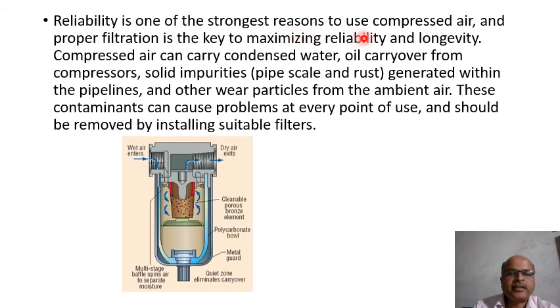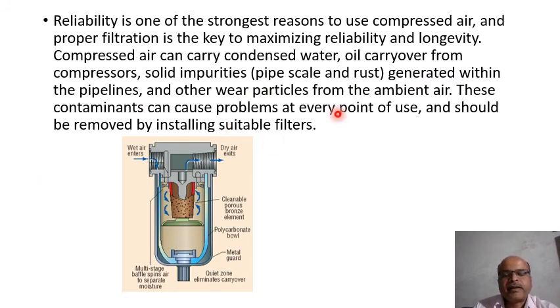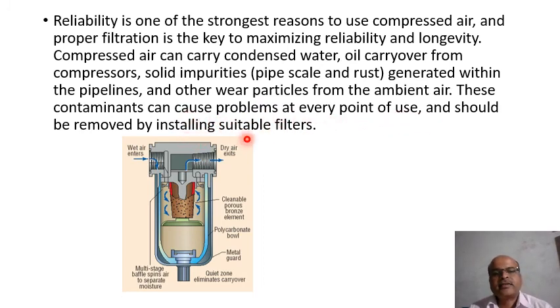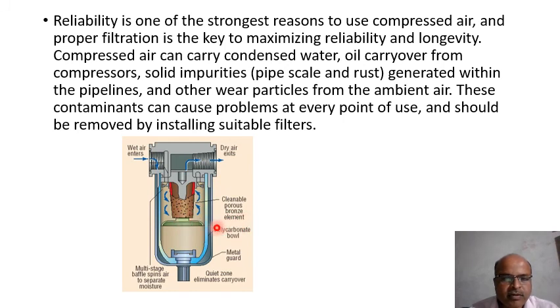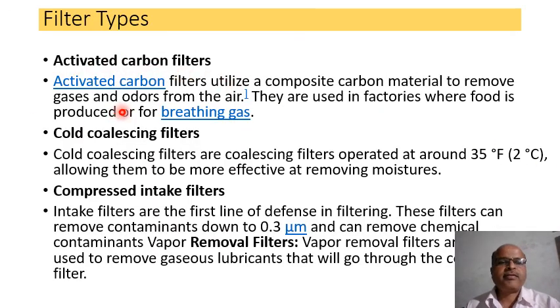Reliability is one of the strongest reasons to use compressed air, and proper filtration is the key to maximizing reliability and longevity. Compressed air can carry condensed water, oil carry-over from compressors, solid impurities such as pipe scale and rust generated within the pipelines, and other wear particles from ambient air. These contaminants can cause problems at every point of use and should be removed by installing suitable filters. The wet air enters and passes through a cleanable porous bronze element, polycarbonate bowl, and multi-stage baffle that spins to separate moisture.